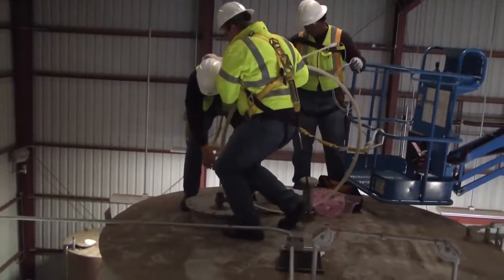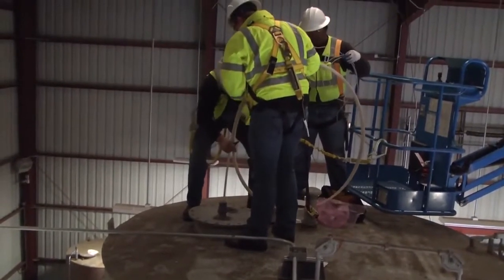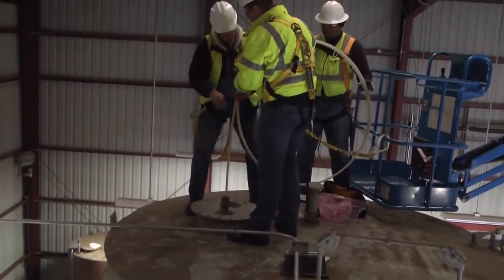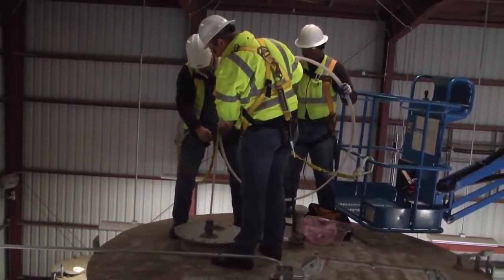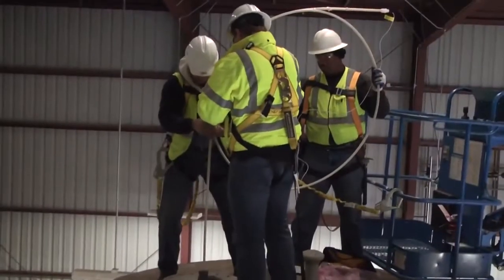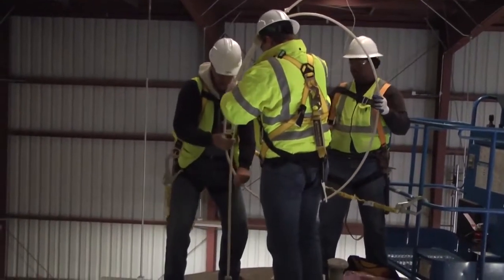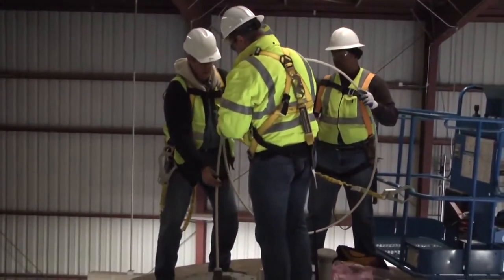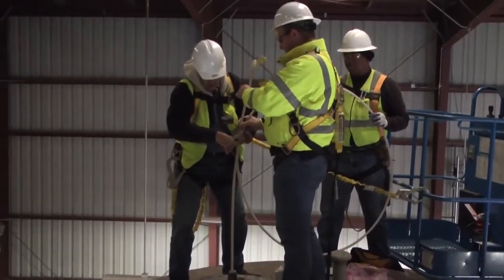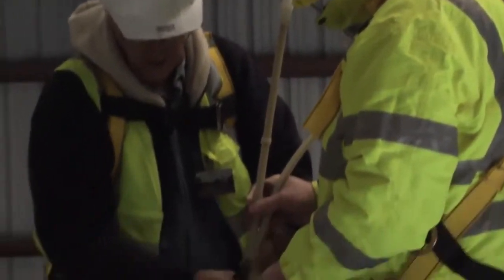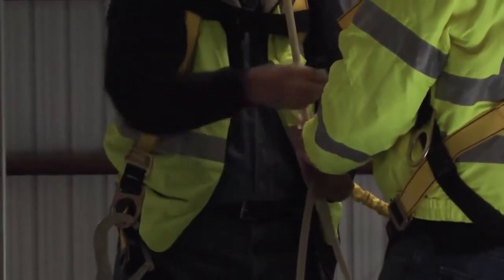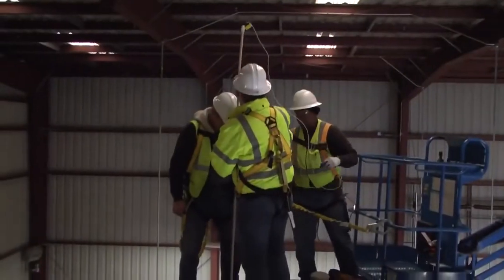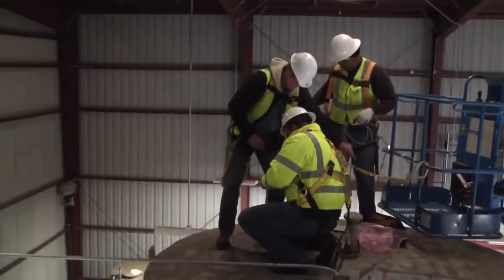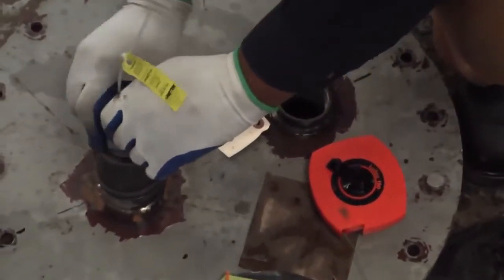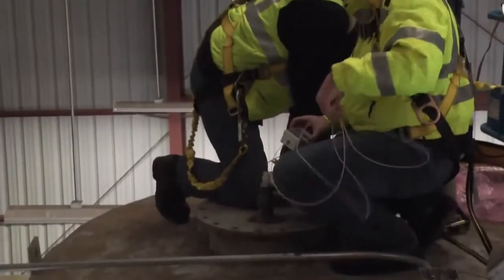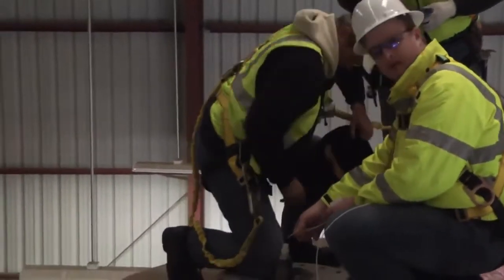Cut the tie wraps one by one as you gently unroll the coil. It's really important now that you have the headpiece exposed. Before you cut this, you want to make sure that you have the top of the probe supported. Remember, grab the probe by the head and do not twist it. Twist the 3/4 inch union piece below it. If you need to twist the probe, make small turns and stop if you encounter resistance. You may damage the electronics.